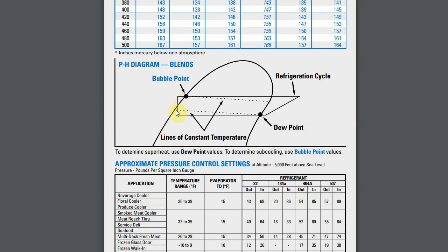So that's dropping pressure to where we leave at our low pressure at our evaporator coil. This is a flash gas, so this is going to be a percentage of saturated liquid and saturated vapor. That's why it's inside our curve here, because it's partial vapor, partial liquid. Mostly liquid, very little vapor. Then as we add heat in the evaporator coil, the liquid is boiling at the dew point.